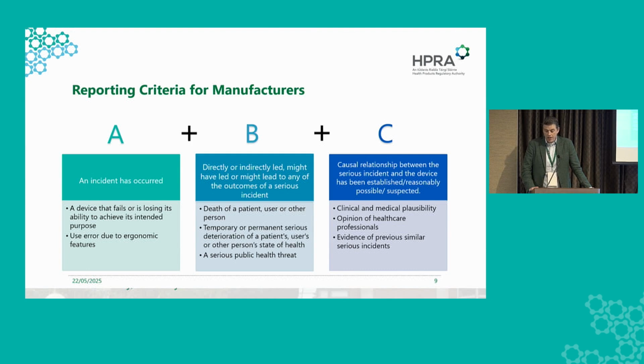It directly or indirectly led to one of the outcomes that I just described. The concept of direct harm is very clear. So something has gone wrong with the device, the patient is injured. The concept of indirect harm also needs to be considered, which means, was there a problem with a piece of diagnostic equipment or diagnostic test that might have led to a subsequent misdiagnosis? So that also needs to be considered by manufacturers in reporting. And then this is really the key bit, and this is where we end up in a lot of discussions with manufacturers.